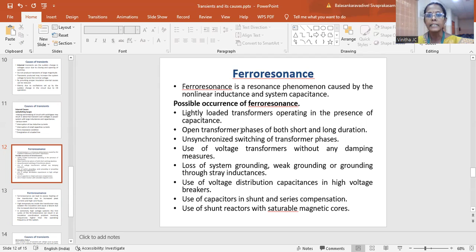And here, the various possibilities of occurrence of ferroresonance conditions are given. First one is lightly loaded transformers operating in the presence of capacitance. Similarly, open transformer phases of both short and longer duration, unsynchronized switching of transformer phases, use of voltage transformers without any damping measures, loss of system grounding, weak grounding or grounding through stray inductances, use of voltage distribution capacitances in high voltage breakers, use of capacitors in shunt and series compensation, and use of shunt reactors with saturable magnetic cores. So these are some factors which may produce the ferroresonance condition.